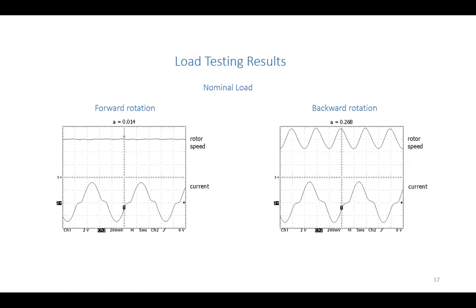And just down here the current waveforms are plotted. As you can see here, at near zero current, the current's quite pinched. That's caused by the saturating bridges, which I showed you earlier, becoming unsaturated at low current because there's very little current in the windings. That causes the inductance of the windings to dramatically shoot up, which tends to pinch the currents. So that causes the distortion in the otherwise sine wave shape you'd have in the current waveform.